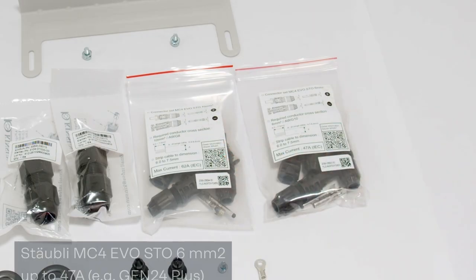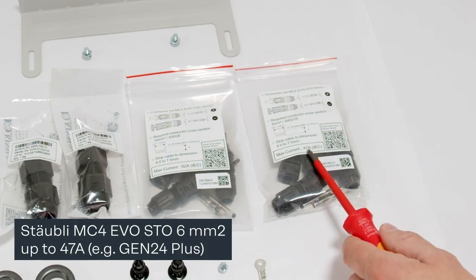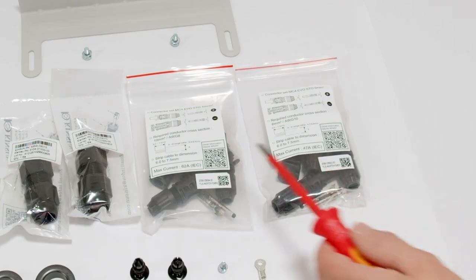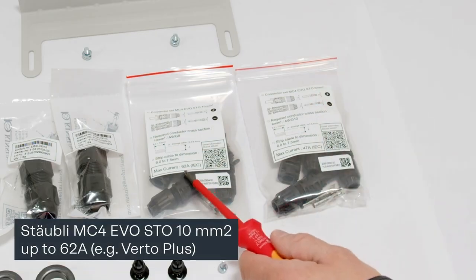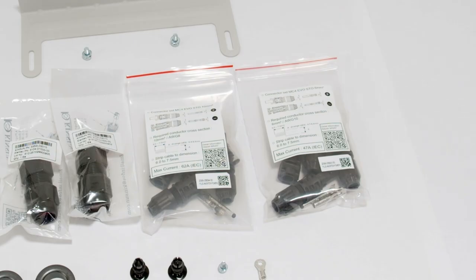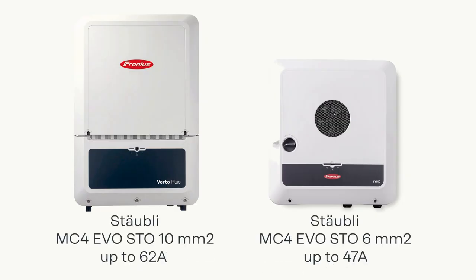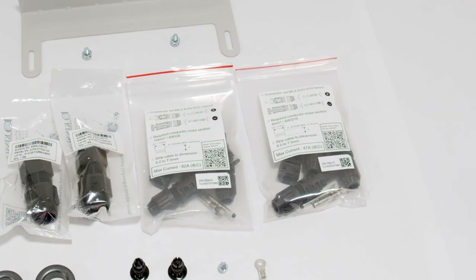Please note that the 6 square millimeter cable variant is good for a current of maximum 47 amps and the 10 square millimeter variant is good for a current of up to 62 amps. So please note, especially with the variant of the inverter that you're installing, that you choose the right diameter for your cable. That means most of the time for the Gen 24 Plus variant, you can use the 6 square millimeter cables with up to 47 amps. And for the Verto Plus, please note that you always take the 10 square millimeter variant with the correlating cable, since this is good for up to 62 amps, since the Verto Plus can do a higher current.